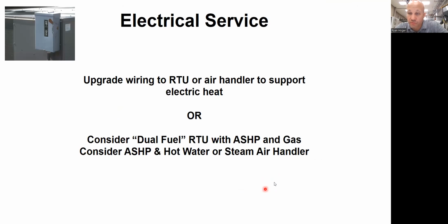Do heat pump packaged units, rooftops, have substantially different weight than fossil fuel or resistance heated units that might present structural difficulties? No, they do not. In fact, you could possibly say that some units are slightly lighter. So if you took a gas-fired rooftop unit off and you put a heat pump version on, you are losing the weight of the gas-fired heat exchanger and the inducer motor on there. And you are gaining the weight of a reversing valve, which is like less than a pound, and electrical heating elements, which is also a couple pounds. So you're going slightly lower in weight, assuming you had everything else identical. You've got the exact same size and the same model and the same efficiency and everything. The heat pump would be slightly less than the fossil fuel version. Not enough to get excited about, but slightly less.